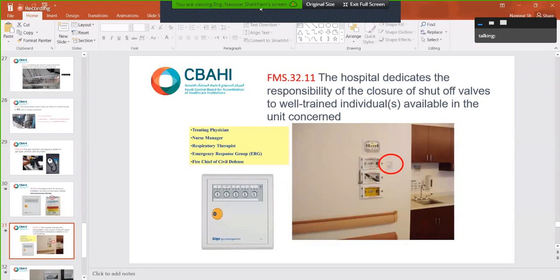We have a utility system failure plan, and a plan B for each system. What you wrote in your plan, you have to apply as a scenario, as a drill, exactly as written. In case of power failure, what you are doing is sending someone to the generator, inspecting the ATS, inspecting the batteries, everything you would do during an interruption.